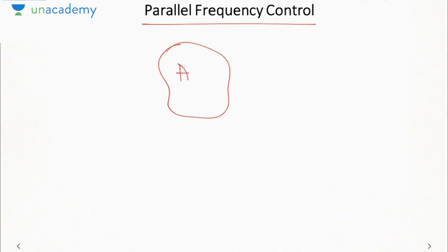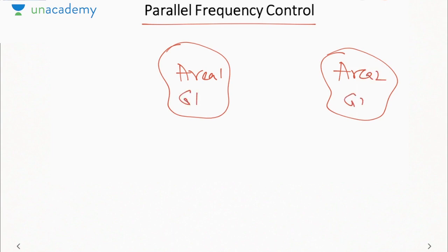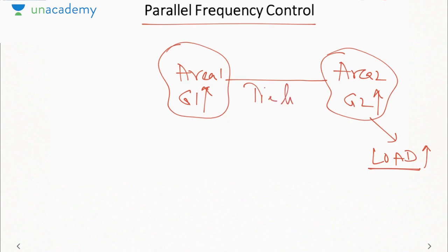That means if this is area 1 and this is area 2, here let us say G1 and G2. Let me say here there is a load which increases. Then what to do is we have to increase generation G2 as well as generation of G1, and we will supply additional power through this tie line. So here both the areas or both the generators are sharing the additional load demand, that is called as parallel frequency control. So here we will try to maintain the frequency constant. We will regulate both the generators together.